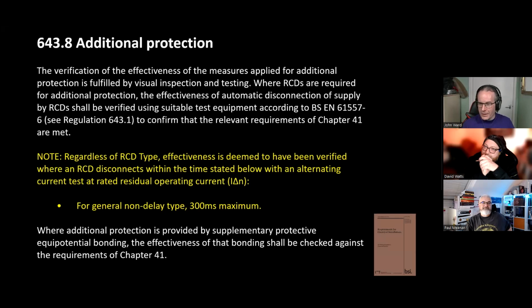in conjunction with that being deleted, 643.8 additional protection, the testing of RCDs. Now the yellow bit is the bit that's changed. So regardless of RCD type, effectiveness is deemed to have been verified when the RCD disconnects within the time stated below with an alternating current test at rated residual operating current. For general non-delay types, it's 300 milliseconds. So this is basically saying, don't bother with a half, and don't bother with the 5 times, don't bother with all that other stuff, and don't bother with the type A and all the rest of it in the testing devices you've got. Just test it at AC at the rated current, and if it trips within 300, all is well, supposedly. All is well.